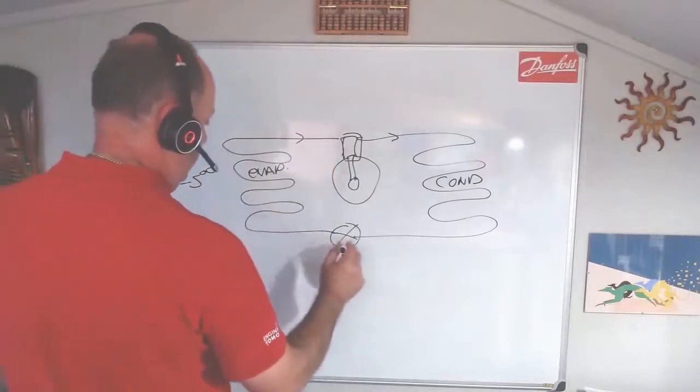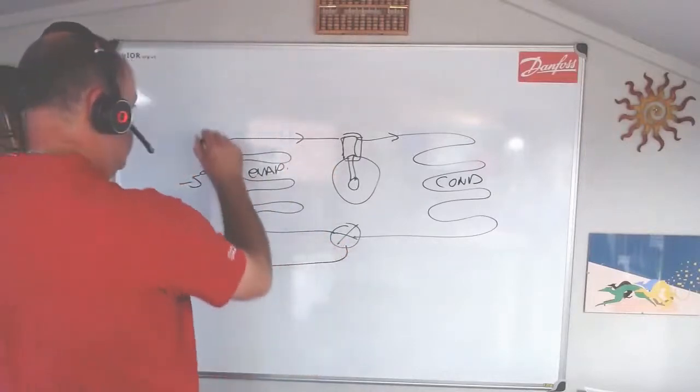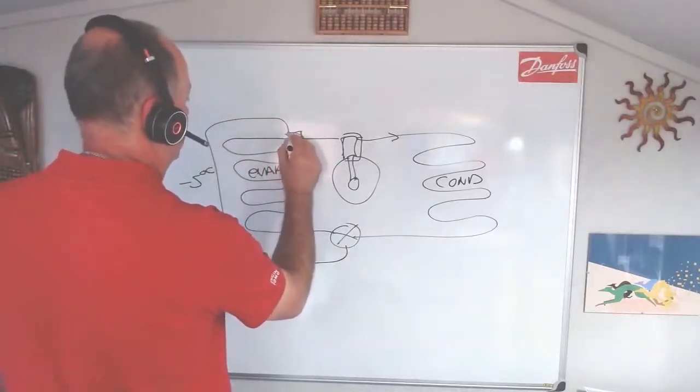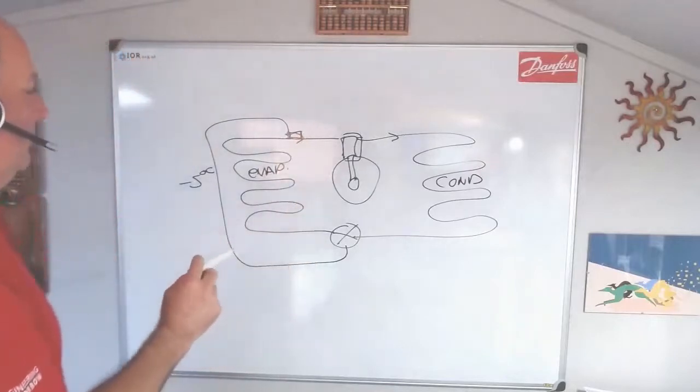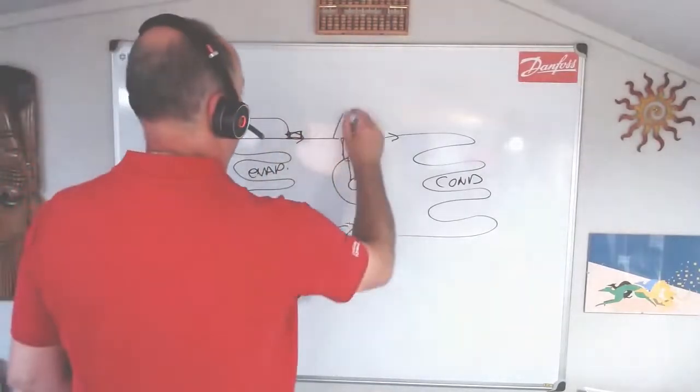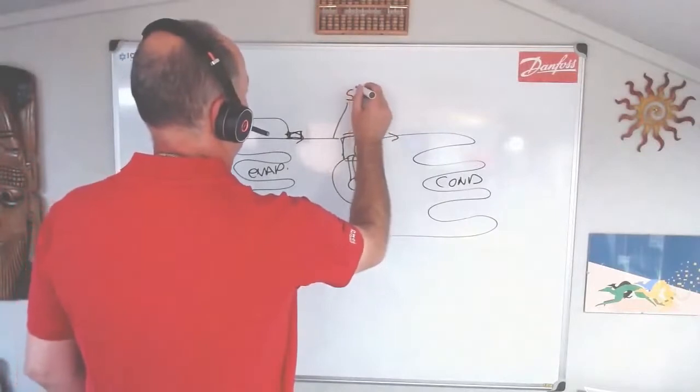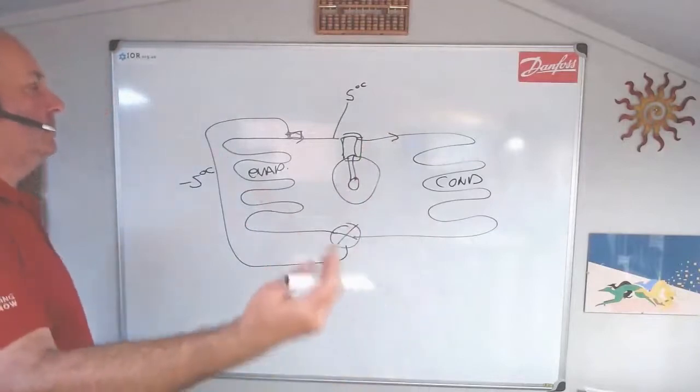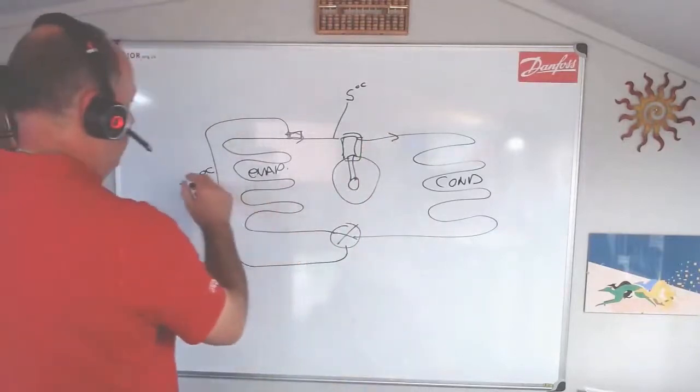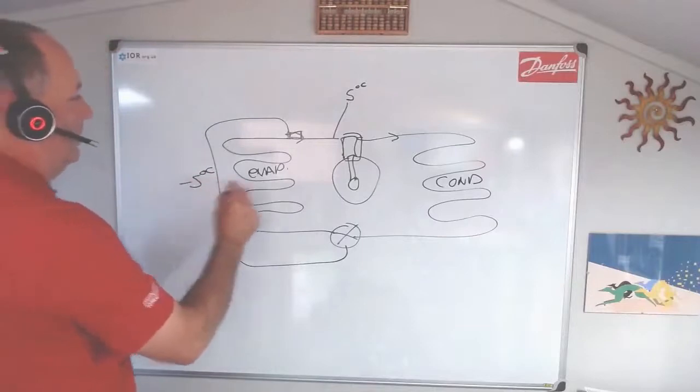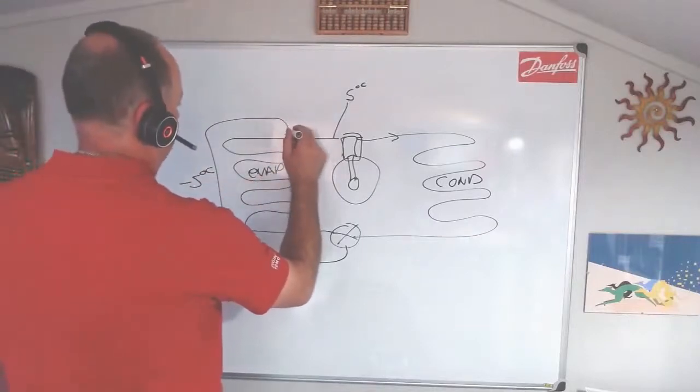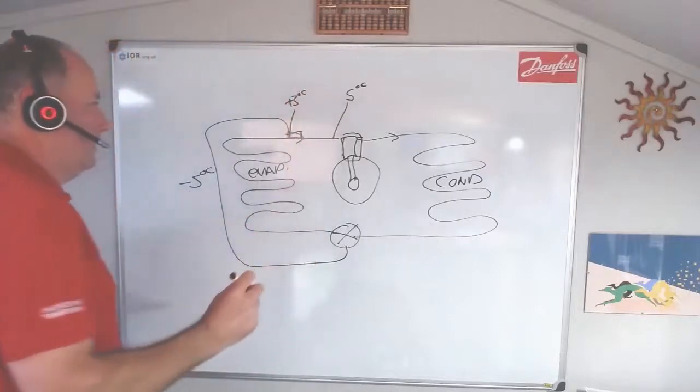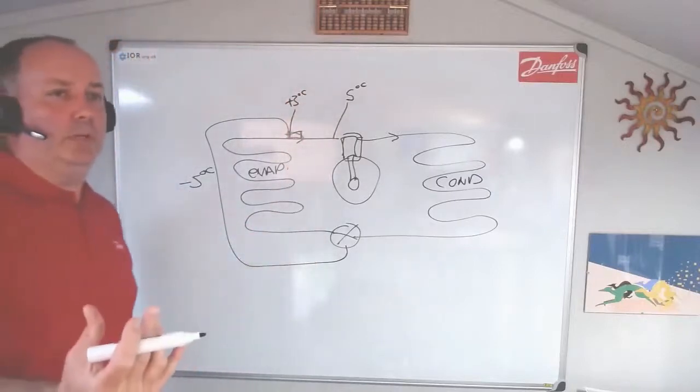So let's say we are evaporating minus five. With our expansion valve bulb, let's come around here. There's our bulb on our suction line. So we're measuring the superheat on our evaporator.